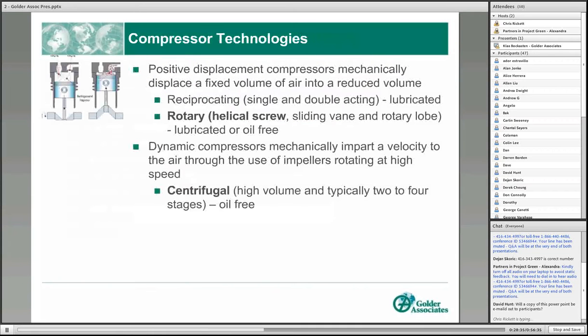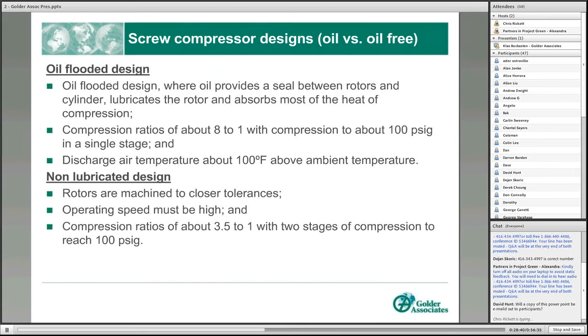Okay, great. So I'm just going to move forward on the slides here. I'm focusing the presentation more on the screw compressor, which is the most common compressor in mid-size facilities. There are two typical designs of screw compressors, either oil-free or oil-flooded. In the oil-flooded design, the oil provides a seal between the rotor and the cylinder. Basically, the lubrication absorbs the heat that Herb spoke of. The compression ratio to reach 100 psig is about 8 to 1, and a single stage would bring you to the pressure required by the plant. Typically, the discharge temperature is about 100 degrees F above the ambient. So in a compressor room, which might be 80 degrees Fahrenheit, you might be dealing with about 180 degrees F on the compressed air.